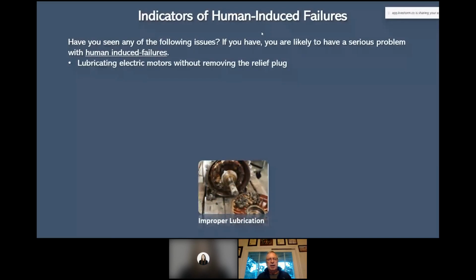Lubricating electric motors without removing the relief plug. Here's a good indication down below. Somebody kept pumping the grease in, pumping it in. All they knew is put 4 shots in. It had a relief plug underneath it. It wasn't a relief, all it was was a pipe fitting. It was supposed to be removed, and you pump the grease as it's rotated until the new grease comes out.